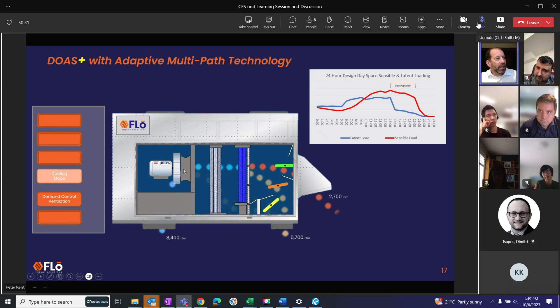And then the last mode, of course, is cooling mode. If we get to this case where we have no dehumidification need, but we need a lot of heating or cooling capability, then we'll bring all of our air streams together. This is very much like that single path unit with outside air, right? Just a mixed air unit at that point. So we have the capability to be just like those other units when it's appropriate for the unit. Fan speed's 100% at this point, and again, maintaining our constant outdoor air volume.